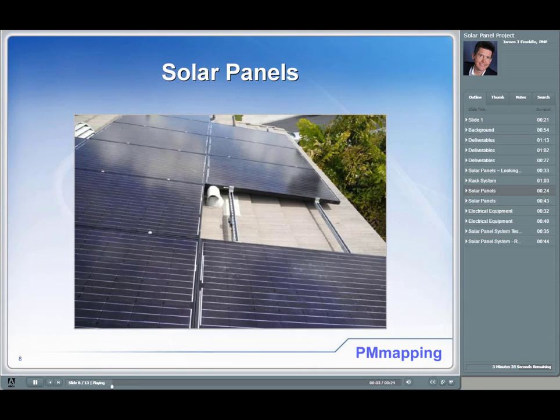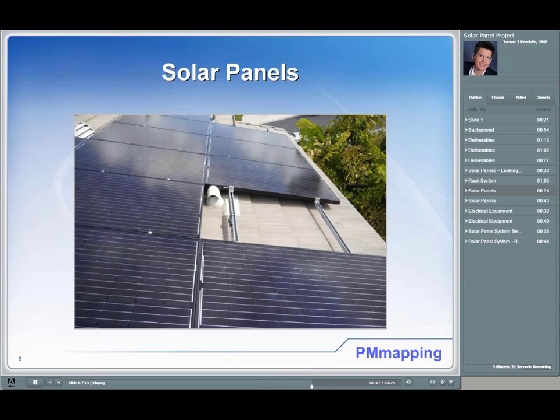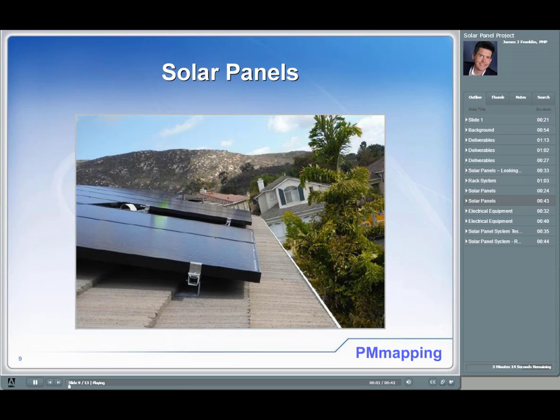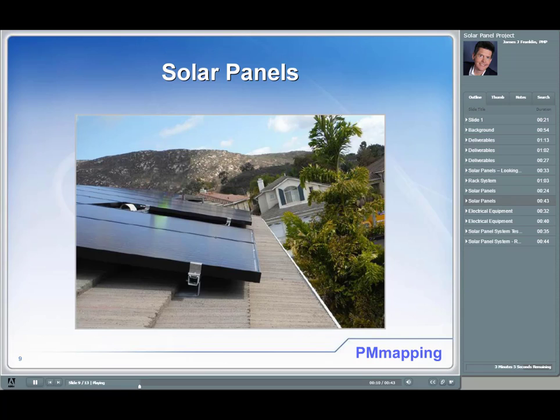This is a close-up view of the solar panels. You can clearly see an area of the roof with a vent where we were not able to install a panel. You can also see the C channels and tile hooks used to connect them. This excellent close-up shows the solar panel sitting approximately five inches above the tile. You want adequate clearance to prevent overheating, but you don't want panels sticking up a foot off the roof — that doesn't look appealing cosmetically. The requirement is a maximum of six inches and a minimum of three inches above the tile.